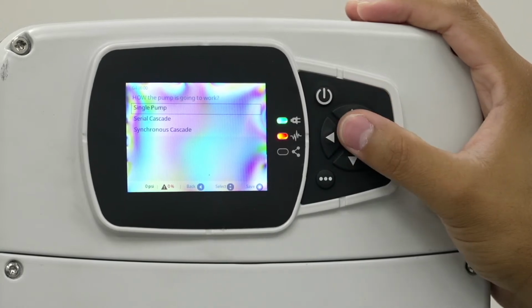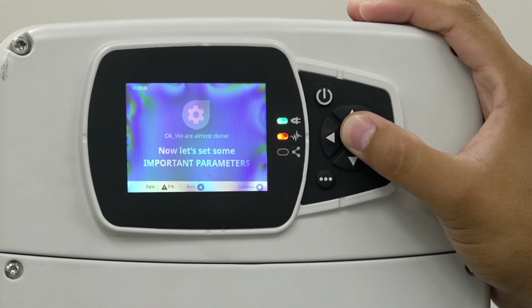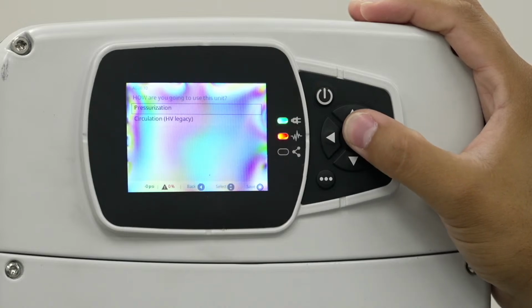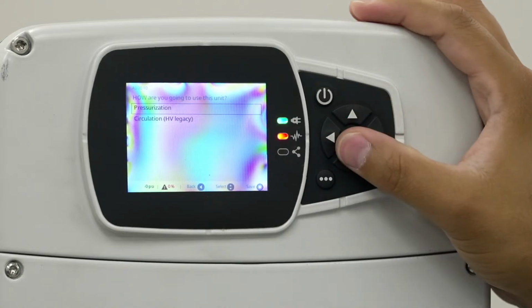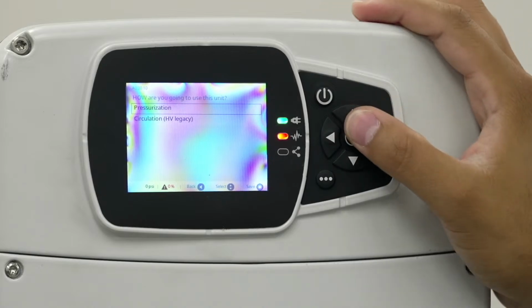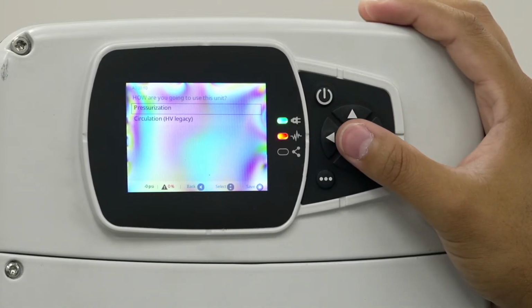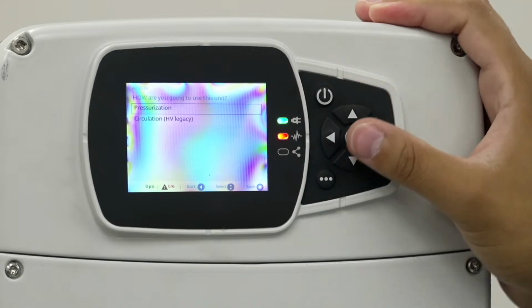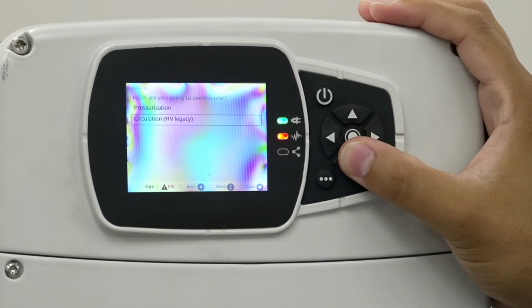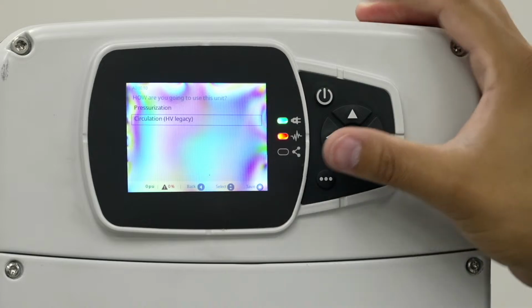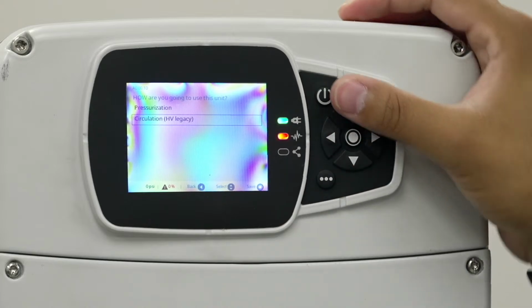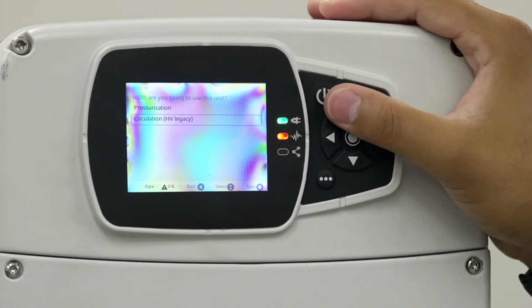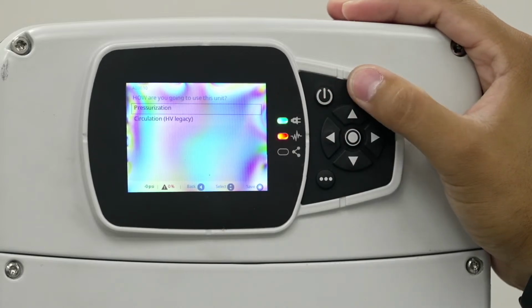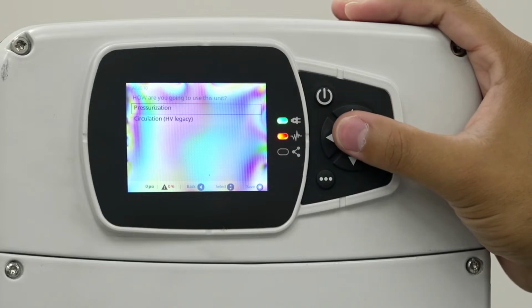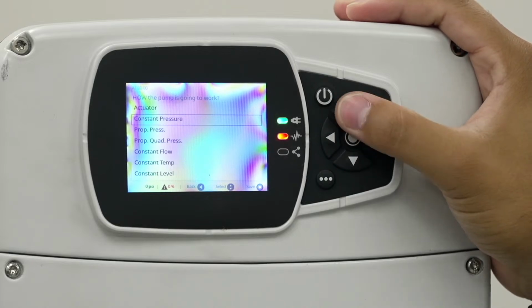But here, we're just going to go with single pump. So we'll do single pump here, saying let's set some important parameters. We'll just click enter to go through there. So here now it's just asking, do we have pressurization or circulation? Basically, pressurization is your open loop applications. You're just trying to maintain essentially a constant pressure. Circulation would be more of an HVAC type system, a closed loop system where maybe you're trying to maintain some differential pressure or something in the system. So for our case, a lot of times we're just simply using pressurization applications. So we'll go with that.